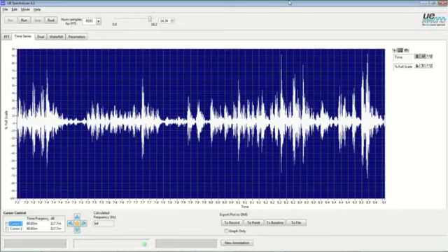However, once a fault has been identified, it becomes even more imperative to increase the inspection frequency to see how fast it is degrading, as well as combining that whenever possible with a visual inspection to find out if the telltale signs of tracking are visible, which would be things like carbon trails and spider tracks, showing where the discharges were occurring.